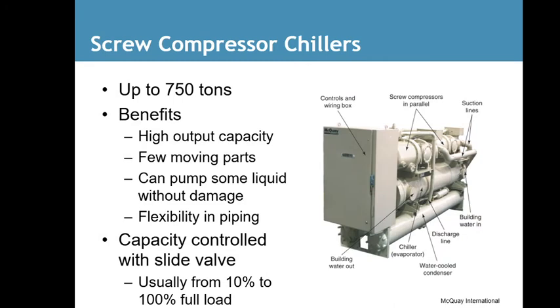Screw compressors for chillers go up to 750 tons. These are probably the biggest. I'm not sure if there's anything bigger than this, but the benefits: they have high output capacity, few moving parts, can pump some liquids without damage, flexibility in piping, and capacity control with slide valves, usually from 10 to 100% fully loaded. So this unit can slow down, and that's what makes them so economical, and pump a lesser amount just by a pressure switch.